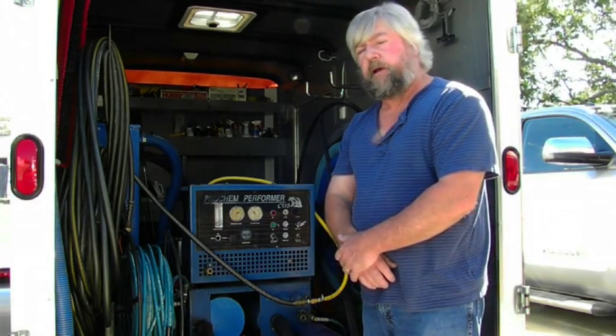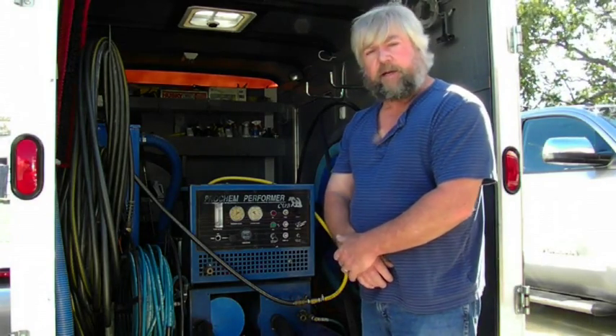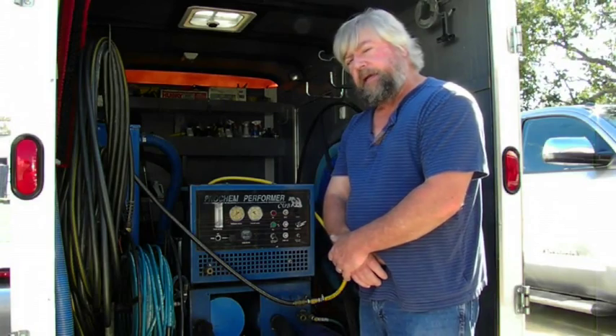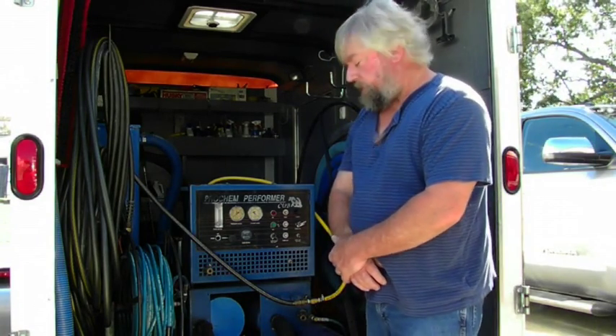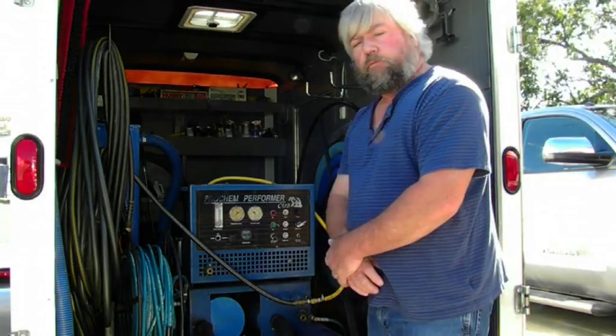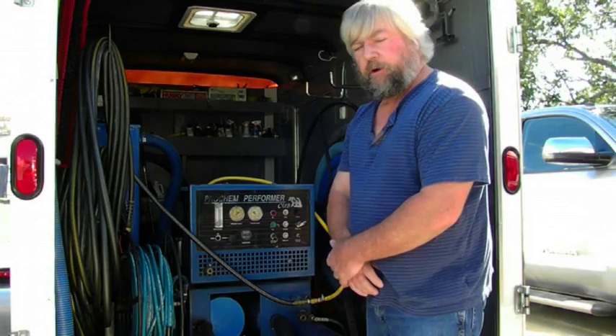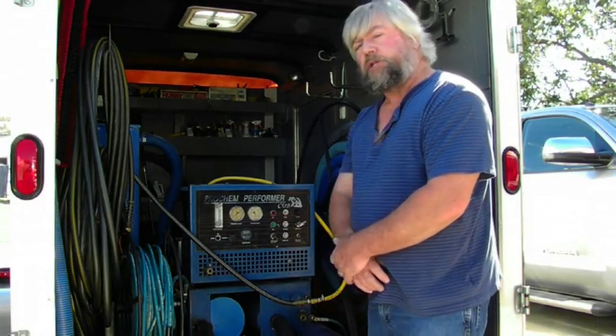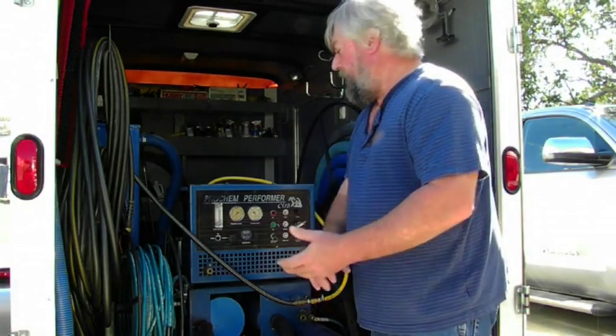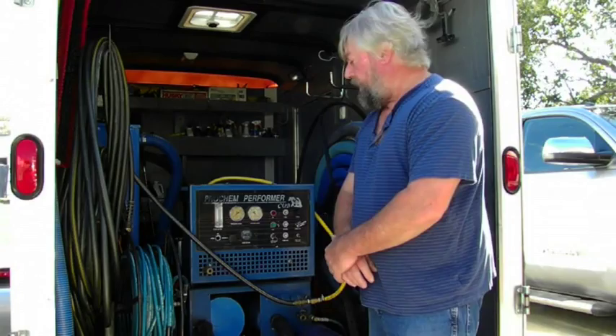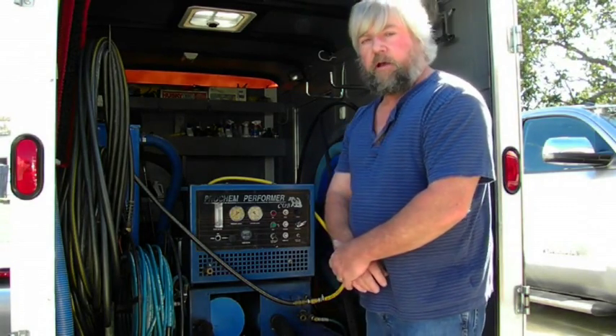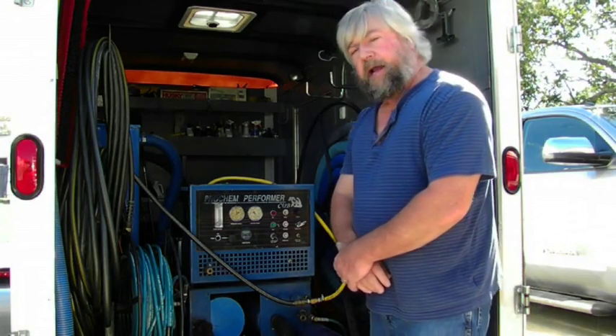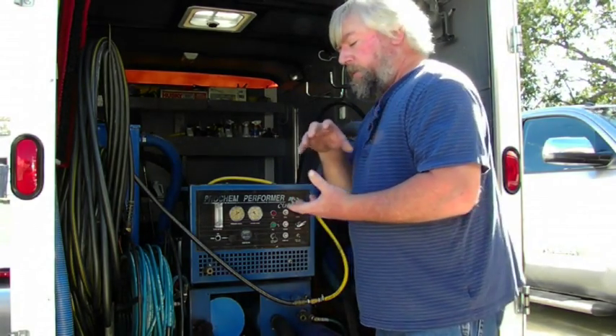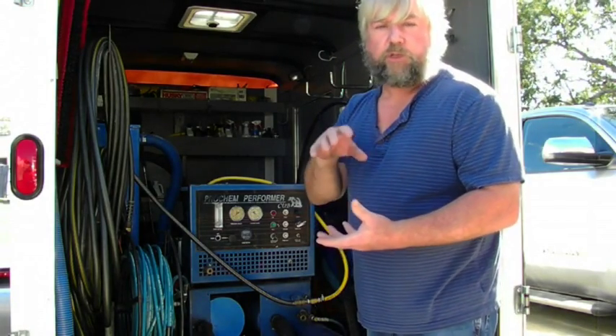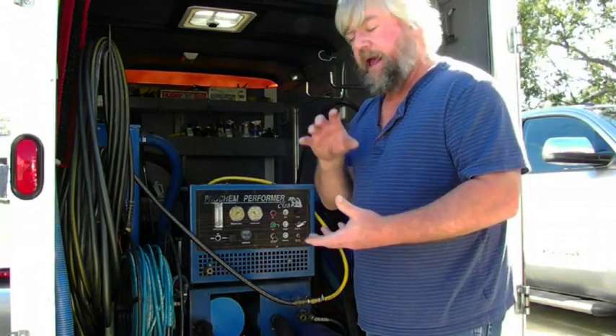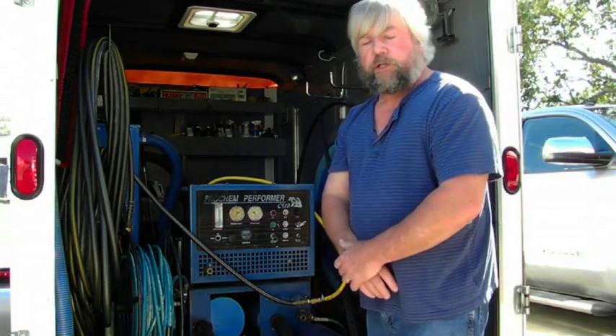The access point heat exchanger has a better design. It's patented, with quicker access to the heat than the helical coil wrap. It has a group of coils where heat rises quickly and transfers very rapidly into the coils. We've also re-engineered the infrastructure so the coil system is supported without metal-to-metal rubbing, which is inherent in a lot of heat exchangers, particularly Prochem's, which have a bracketed metal-on-metal design where the helical wrap is bracketed down to the case. With pulsations from the water system and exhaust, that creates a lot of havoc and wear and tear on that joint, which eventually starts to leak.